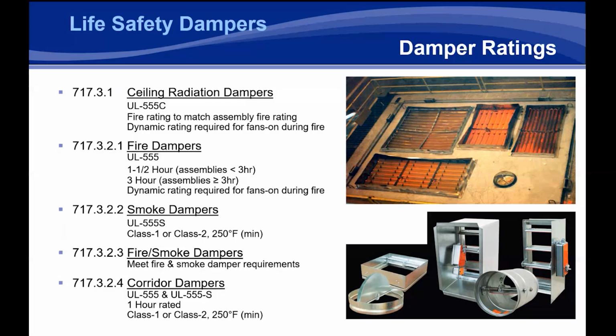The only floor ceiling assemblies that I know of that are dynamically rated are wood truss, which aligns with most of your multifamily construction that will see this need for these air handlers that don't automatically shut down, creating a dynamic system. But the big problem there is they're all required to have fully steel duct in the floor ceiling assembly. Most floor ceiling assemblies use flex duct. It's much cheaper. And that addition of fully steel duct throughout the assembly, throughout the building complex, or throughout the entire apartment complex would add a massive amount of cost. And as soon as any engineer, contractor, building owner is going to see that cost, they're going to pivot to switch to a way to create a static system to be able to utilize that flex duct.